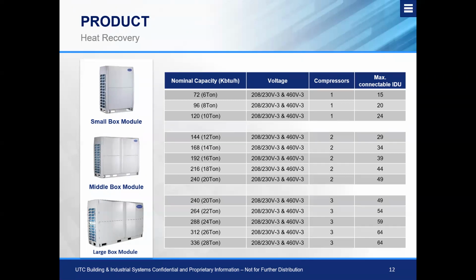So when we're looking at carrier product, our small box module will range from 6 to 8 tons, and they'll offer 1 compressor per outdoor unit. Depending on the tonnage we're working with, that will dictate the total number of indoor units that we can connect to that system. So it's certainly important to reference this chart, and if you don't have some referencing material in front of you, I always suggest that you reach out to me via email, phone, or anyone here at Standard Air Lite who can advise you of the maximum connectable indoor unit number, so that we're not designing a system that will not be able to work.